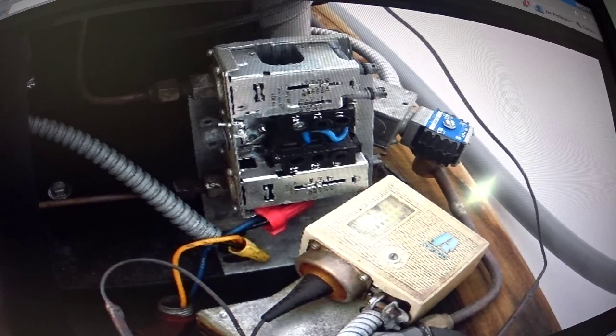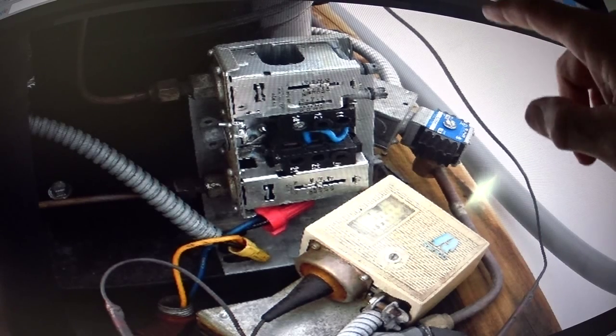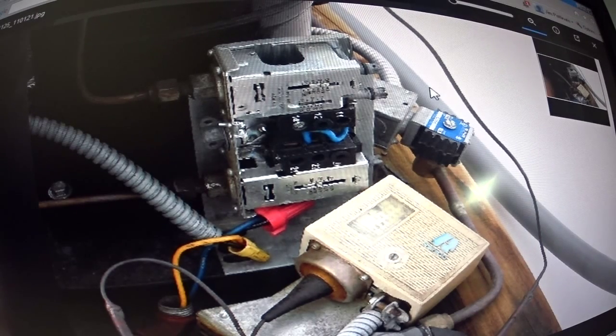Okay, this is on a refrigeration unit on a roof to a wine cooler. This glass door wine cooler in a store. Now I installed this condensing unit a couple of years ago, maybe 2.5, 3 years ago. And in the interim between then and now, the customer wanted to save money, so he got somebody inexpensive to work on it. And apparently the compressor went bad, and I found the old compressor sitting over to the side over this way.